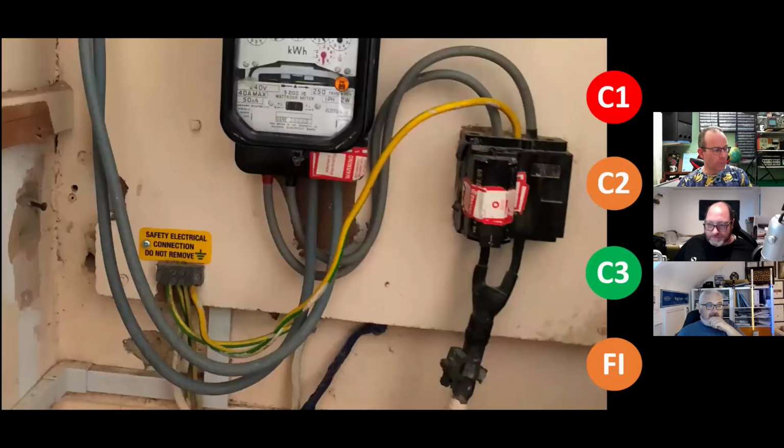So this disaster, this mess, this horrible installation, John Ward recognises it straight away because it's my house. It's downstairs. So what is that? What supply is that? Because there's evidently a BS951 clamp on it, but there's also a link into the DNO head. So it's evidently maybe a converted one. But what does everyone think, and what would you code that? Or if you saw it, would you code it, is probably a bigger question.